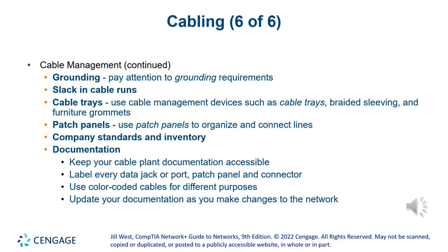So usually the wire will go from a specific port on the patch panel to a jack on the wall. If the patch panel has ports from 1 through 48, you want to make sure that the jack on the wall you label with a number 1, so you know that that cable goes to the patch panel, position number 1. If you have more than one, of course you have to start changing the numbers. On the next patch panel, even though it says 1, you start with 49, 50, 51, and keep going until you get to 96, and then match the labels to that.